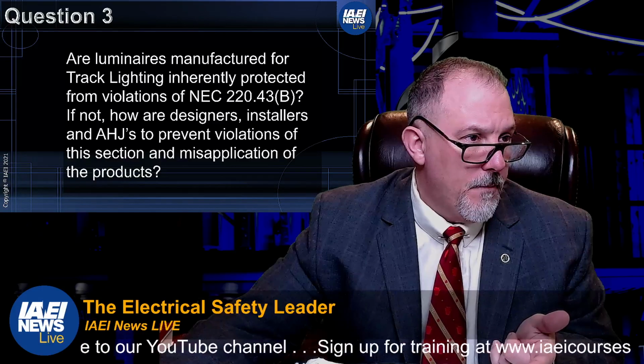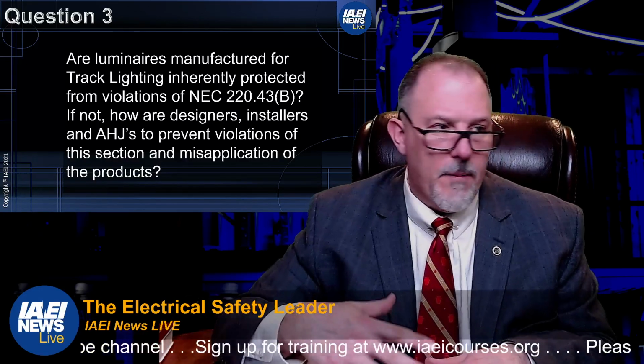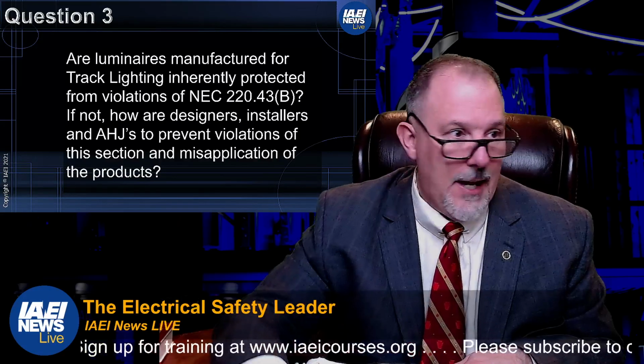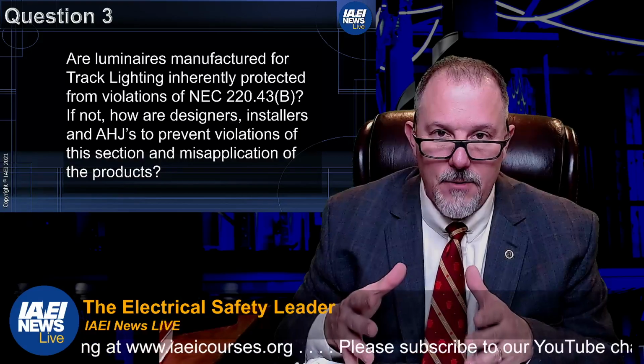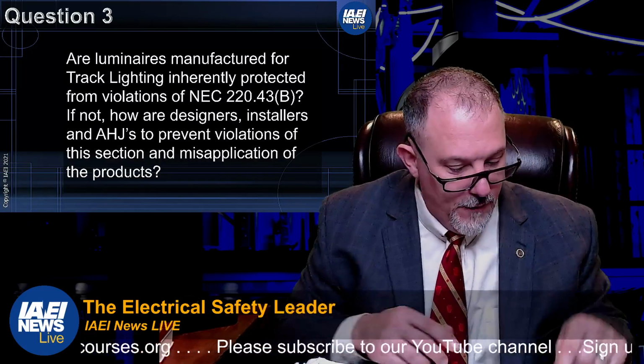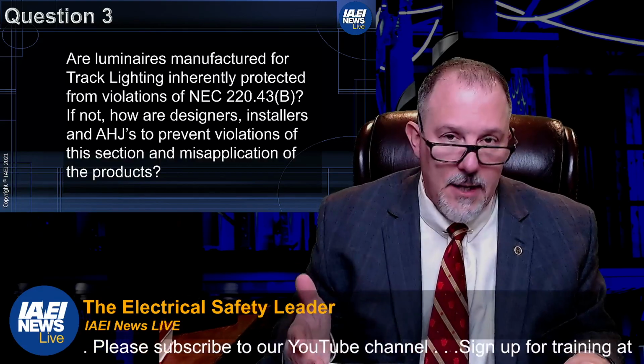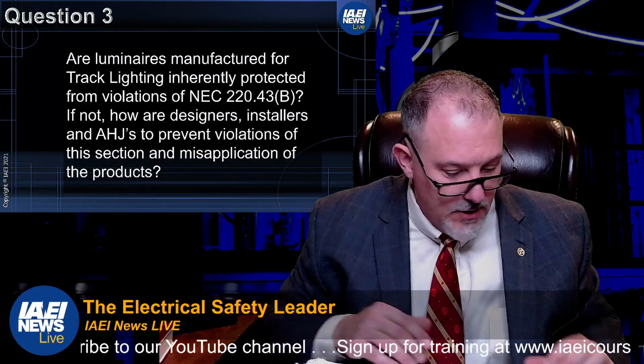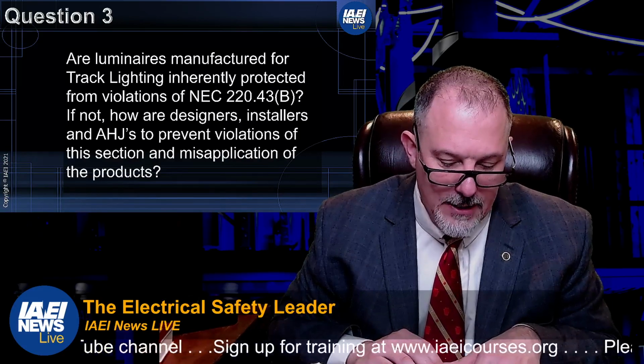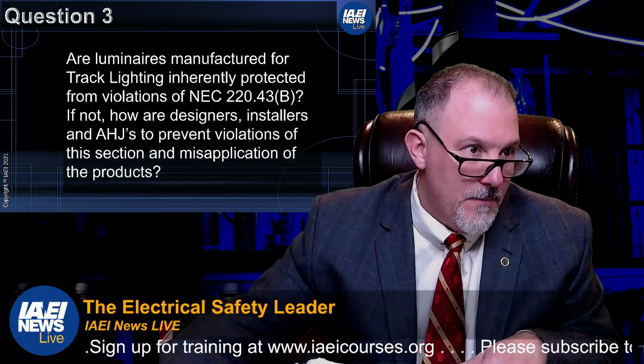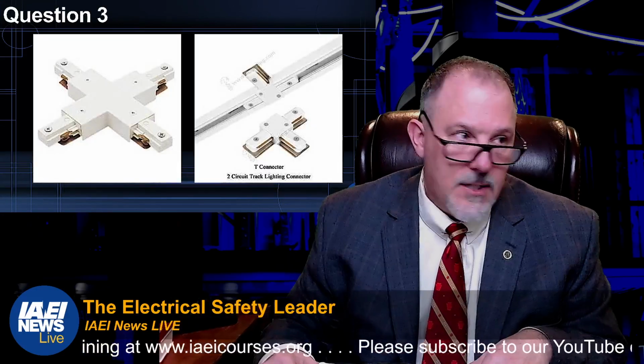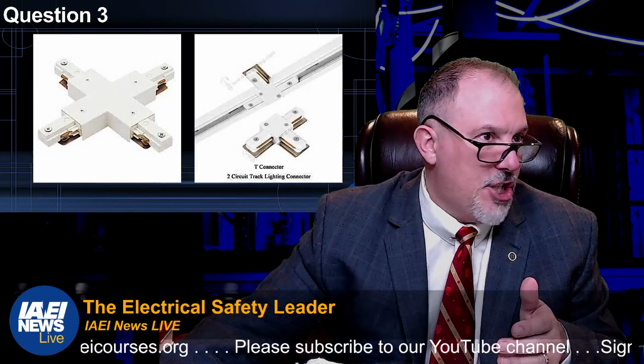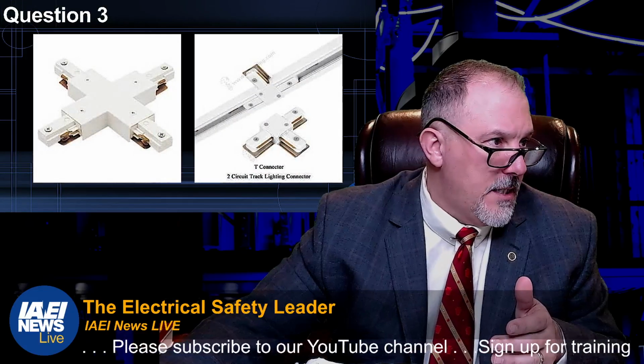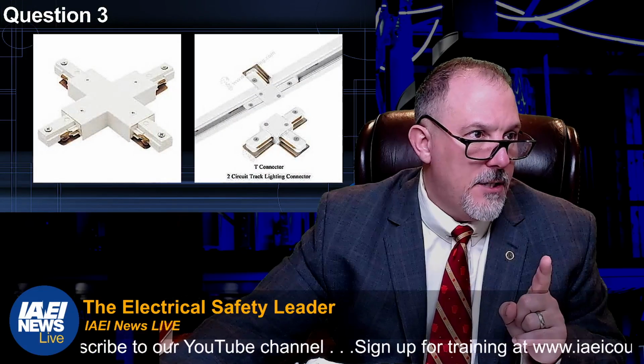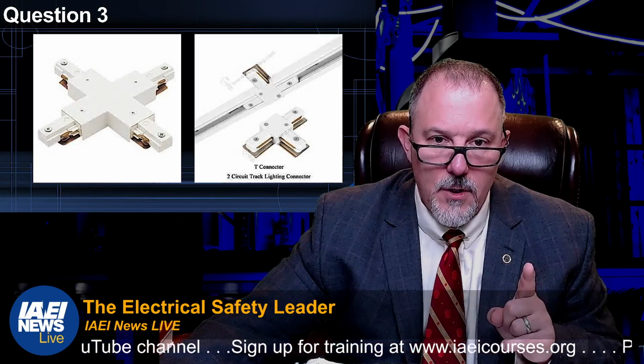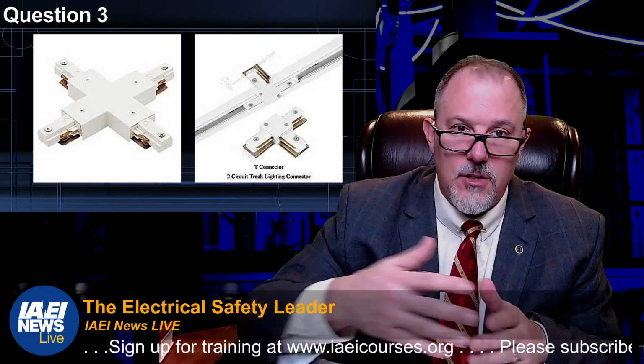From a designer and an installer perspective, and the AHJ, we've got to work together to figure out how to do the proper calculation for feeders and service load calculations. If you're using a lot of track lighting, you've got to think about these requirements that are basically every 2 foot of track lighting, you're adding an additional 150 VA. Why is that? Well, when you look at track lighting, they're expandable, right? They can change. These devices are expandable, and you can put more lighting solutions on the track.